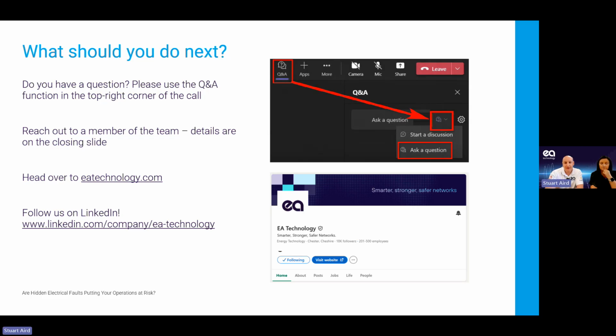Is our portable detector applicable to GIS switchgear? Yes. Again, we do have other sensor types. We have the band joint sensor, which can be put onto the bands between each GIS cubicle. When we talk about GIS here, I am referring to the tubular GIS above sort of 132 kV voltages. That will pick up PD from that. HFCTs can also be used on that type of equipment, but generally it would be the UHF band joint sensor. That type of equipment sometimes comes with built-in sensors, and again, the UltraTEV Plus2 can be connected to those as well.